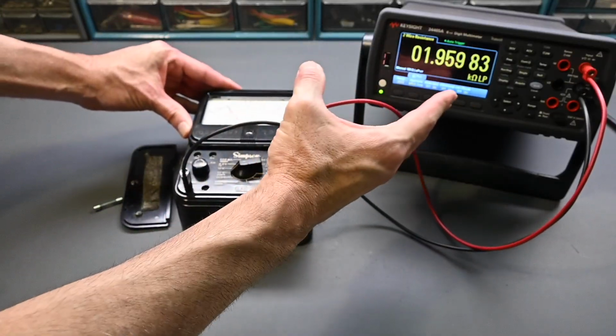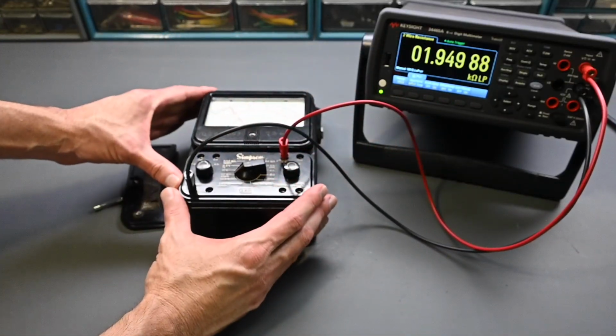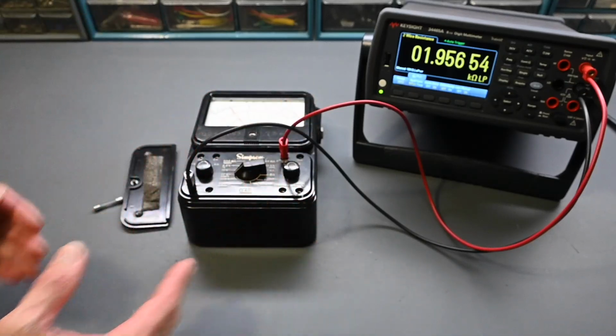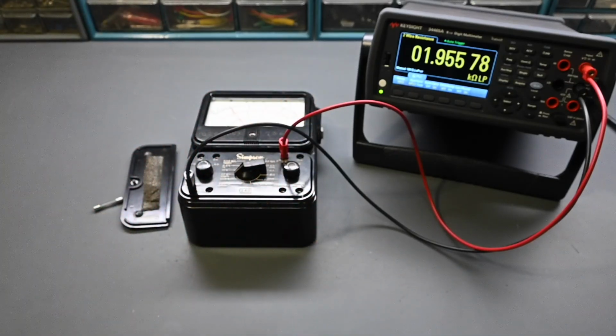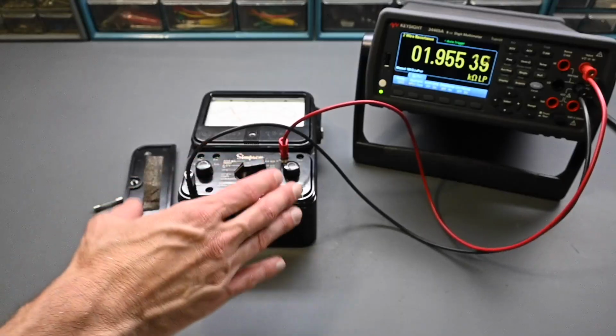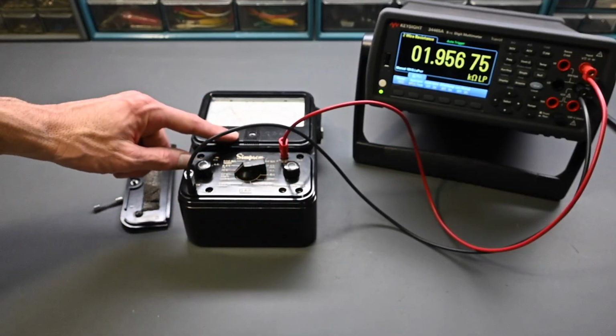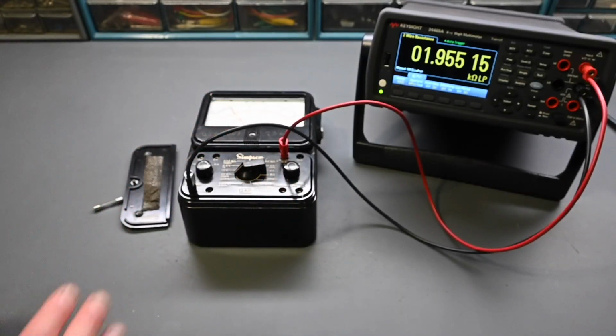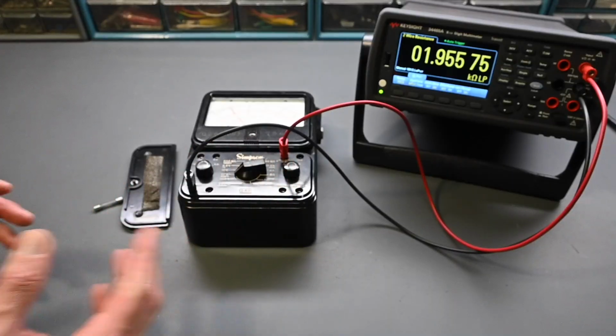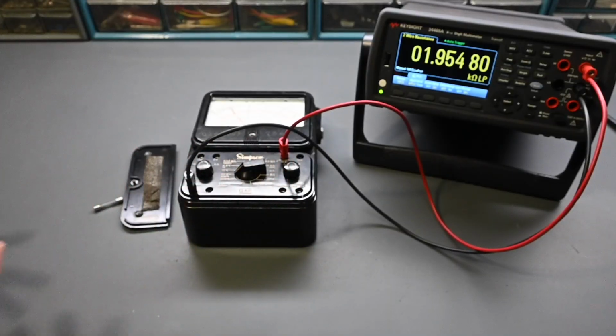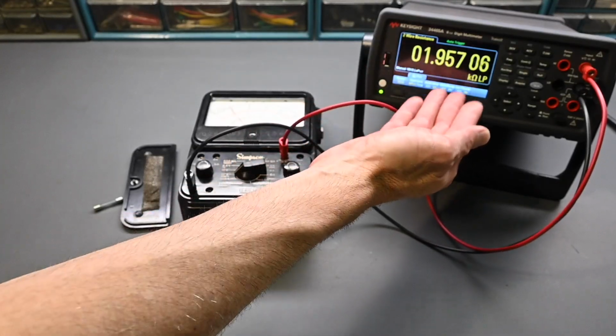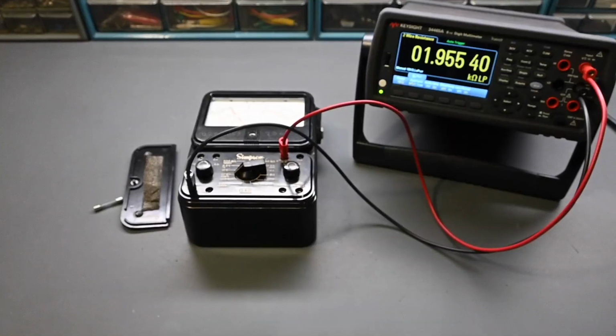The reason I'm sneaking up on the meter and taking these measurements is that I don't want to put voltage on it to start with, because if multiplier resistors are damaged or there are other problems, I don't want to damage the meter movement or other components. So this is a way to take some measurements and sort of sneak up on the meter to get an idea of what's going on. We can see right now there is a problem, so it's definitely not going to be accurate when you're seeing 2K ohms at this point.